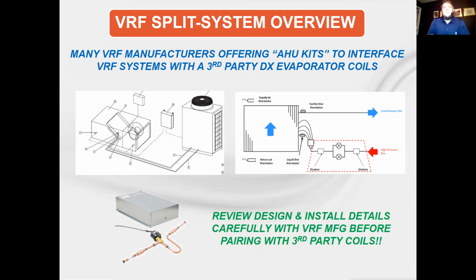So if you look here, this is our outdoor unit and it's connected with refrigeration, similar suction and liquid lines, we can call them that, but there are all sorts of mixed phases in a VRF operation. Those are paired with an evaporator coil that is not manufactured by the VRF manufacturer. Most often in VRF systems, any indoor unit, whether it be a high wall, cassette, whatever it is, is manufactured, designed, and pre-tested with the outdoor unit ahead of time. So it comes as sort of a package.